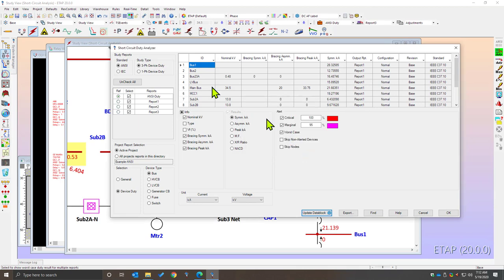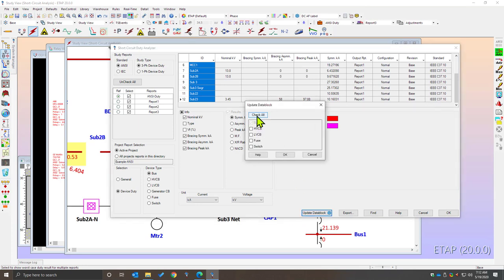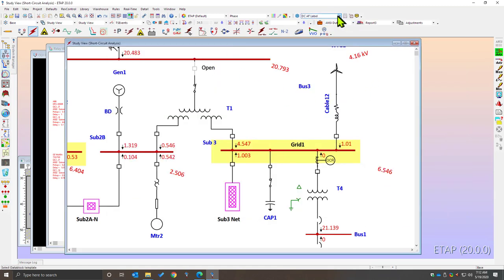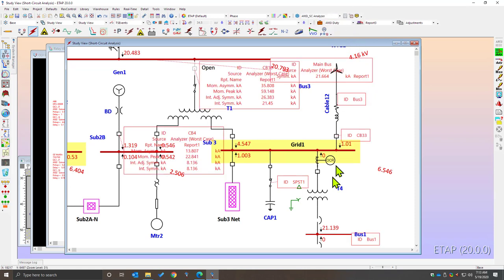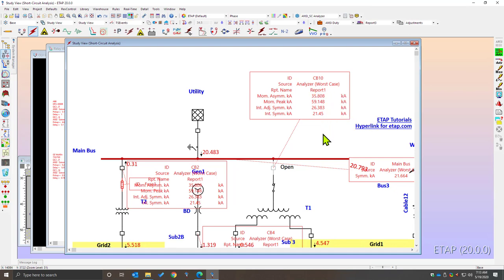You can easily see short circuit values from different reports or view worst case values and which report they are derived from. Simply update the data block by selecting the buses and component types you want to update. Go to your diagram, select the appropriate data block, activate it, and evaluate the information on the one-line diagram. You can see for this circuit breaker the worst case result is coming from report number one. You're now ready to print your one-line diagram and produce a high quality deliverable for your short circuit study.